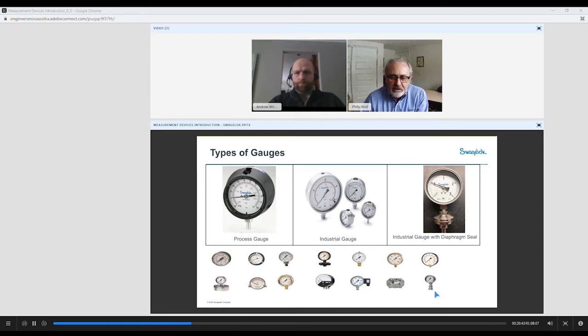Down here we have a diaphragm seal on the bottom. This is used in sanitary applications, food processing plants or those types of things. Again, a diaphragm. Here we have an electrical connection. You may want to have set points on here for a max or min that would send a 4 to 20 milliamp signal back to a panel. Differential pressure gauges as well, vacuum gauges. So many different gauges and types of cases, and panel builder gauges, and you know, plastic cases, brass cases, various other materials are available as well.